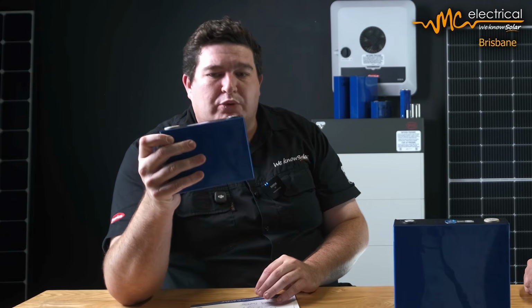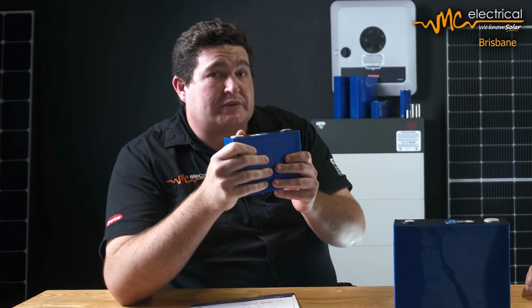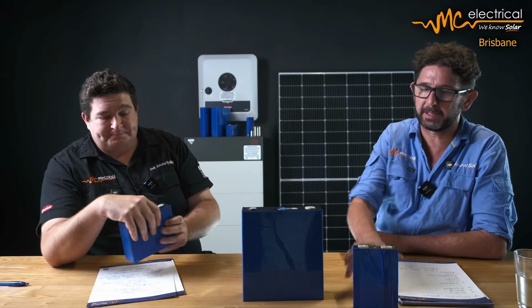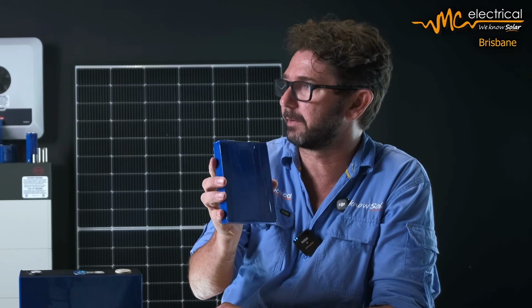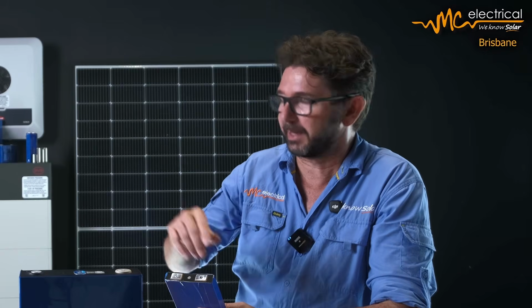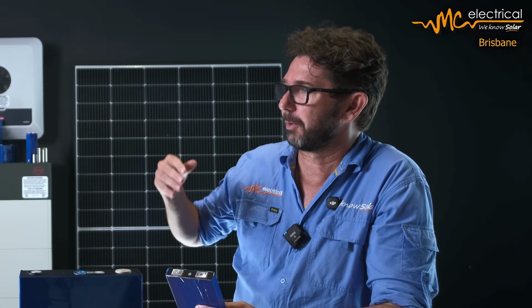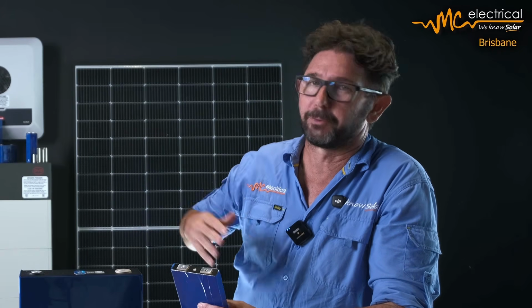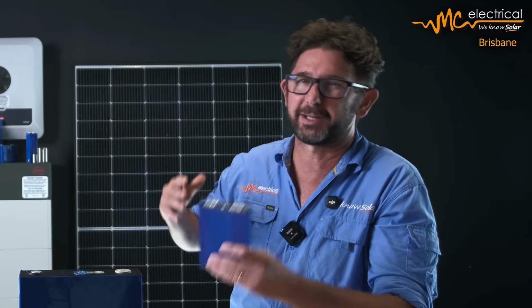So there is a real advantage of using slightly smaller cells. They just don't get anywhere near as hot because there's not as much current running through them. The disadvantage is that when you keep stringing it together, you end up with a lower voltage, so you get to a higher voltage quicker, meaning you can only get like a 20 kilowatt hour battery with this one. Whereas with this one here, you can get up to a 50 kilowatt hour battery.